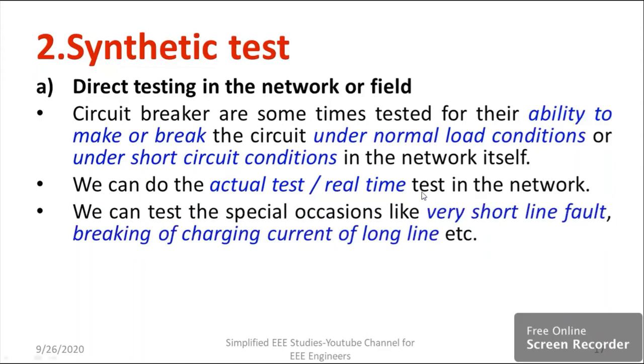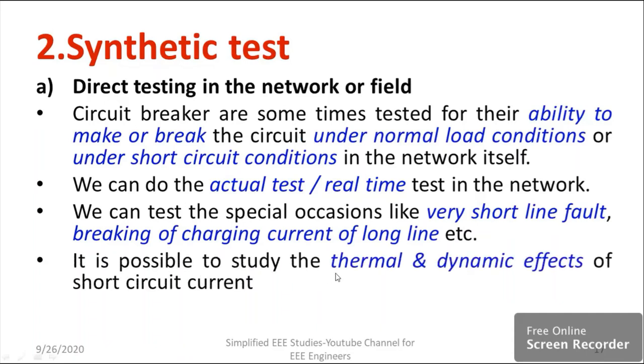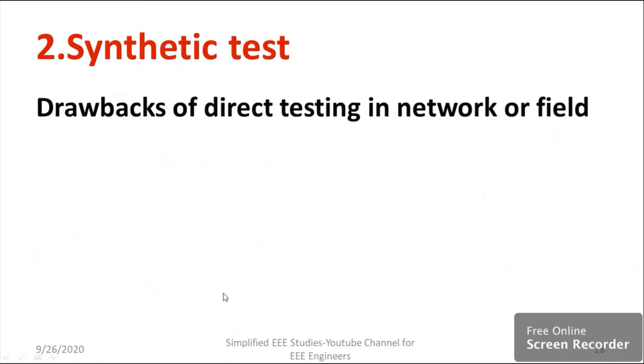We can test special occasions like very short line fault, then breaking of charging current of long line, etc. These are the specialties. It depends on the network which you are going to use. If the network has frequent faults, that is well and good to check the performance of the circuit breaker. It is possible to study the thermal and dynamic behavior of short circuit current. That is also feasible.